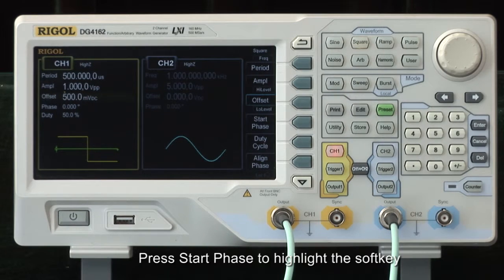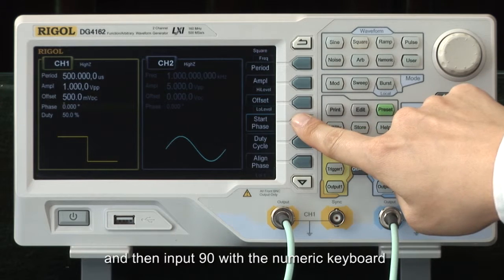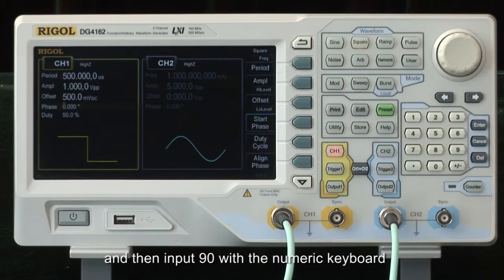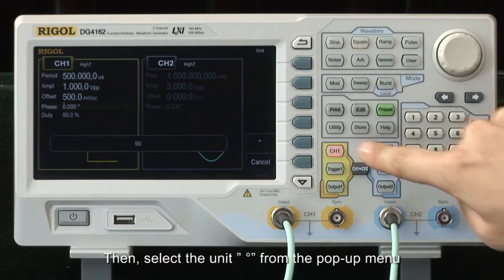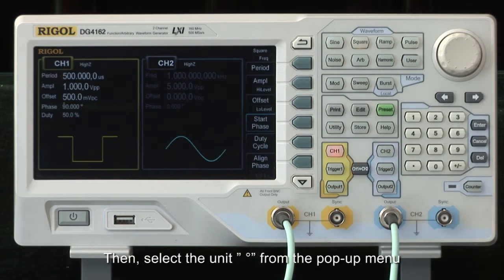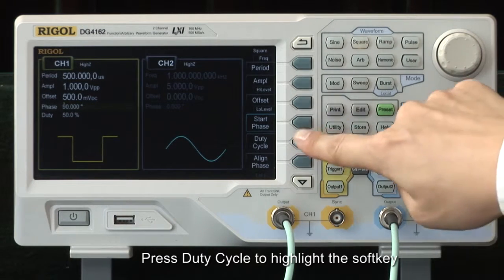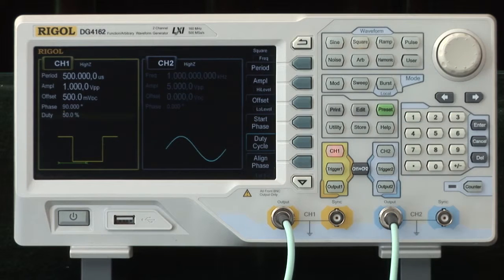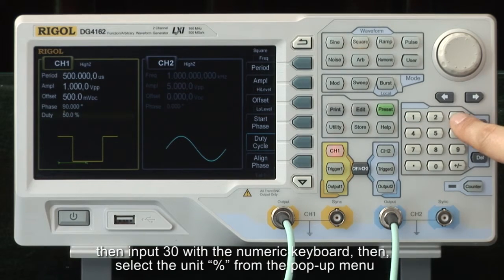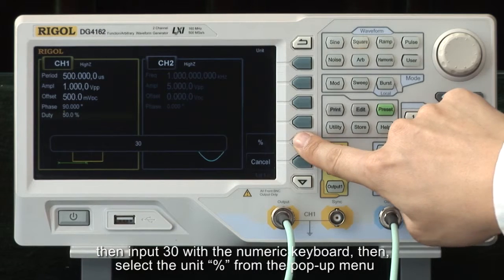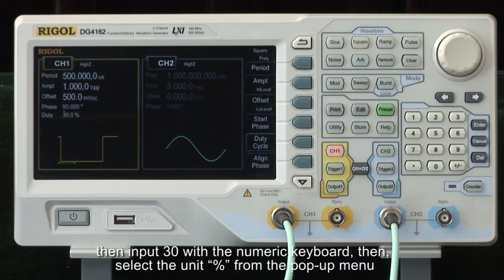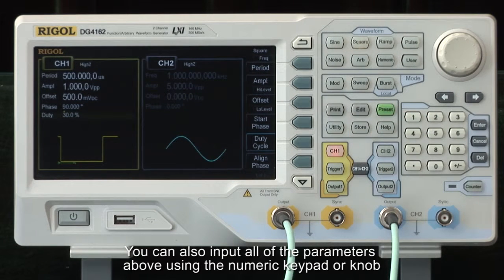Press the Start Phase key to highlight the soft key, then input 90 with the numeric keyboard. Then select the unit degree from the pop-up menu. Press Duty Cycle to highlight that soft key. Then input 30 with the numeric keyboard and select the unit percent from the pop-up menu. You can also input all of the parameters above using the numeric keypad or knob.